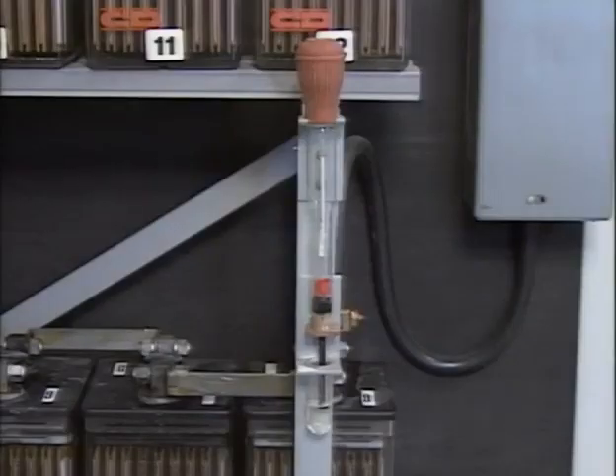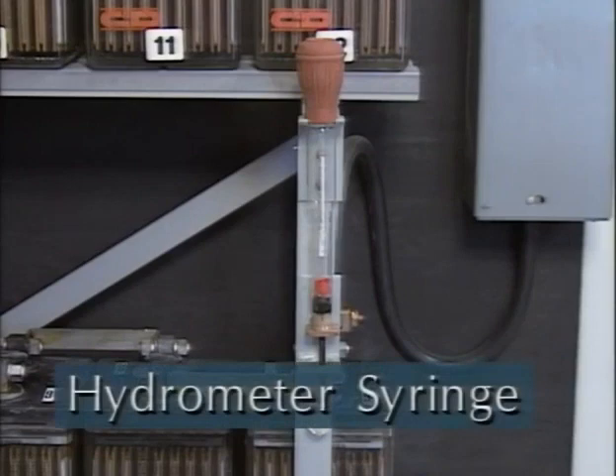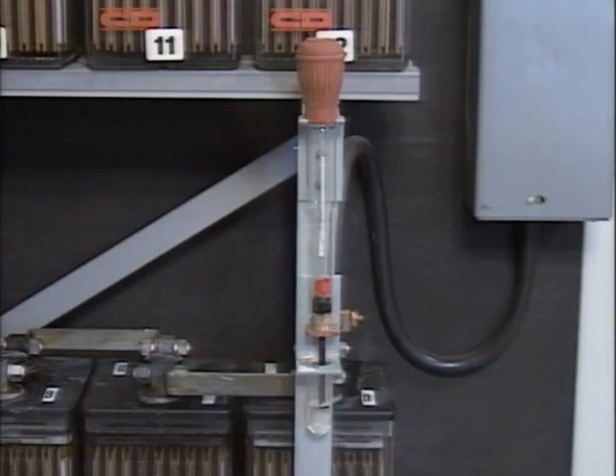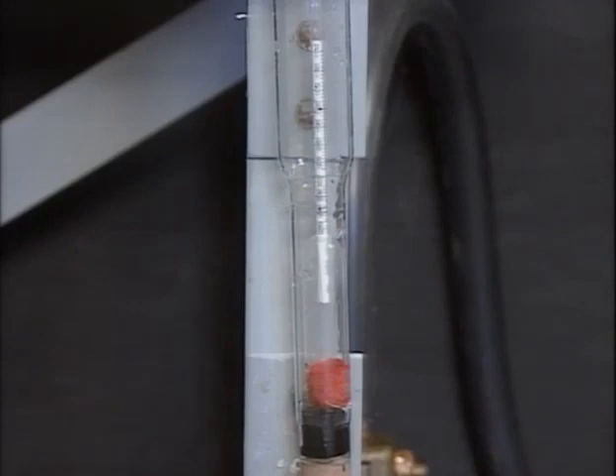Specific gravity is measured using an instrument called a hydrometer syringe. Most hydrometer syringes have the same basic parts. At one end is a rubber nozzle that's inserted into the cell. At the other end is a rubber squeeze bulb for drawing electrolyte into the body of the hydrometer. The body is a glass barrel.